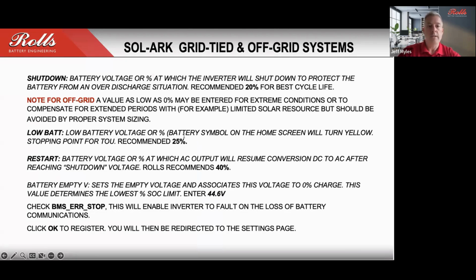So the off-grid, there's a couple notes here regarding low battery and restart. One thing to consider with the LFP products, if you're switching from a lead product, for example, and doing a retrofit on a system, the state of charge of the batteries, depending on the storage of the units and so on, is going to be very different than what you would see with traditional lead batteries. So traditionally, if it's a seasonal property, the recommendation has always been fully charge the units and then disconnect the system. In this case, you don't necessarily need to disconnect, but you do want to ensure that the batteries are maintained at an adequate voltage.